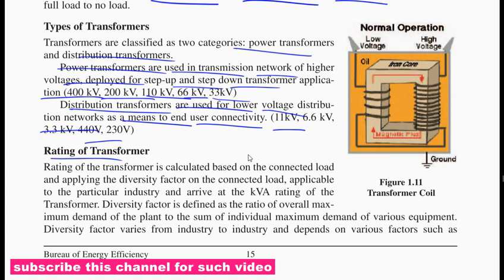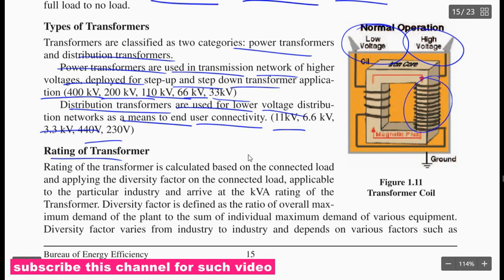The transformer has coils: a low voltage coil and a high voltage coil. This is called the high voltage coil, this is called the low voltage coil. Rating of a transformer is calculated based on the connected load and applying the diversity factor of the connected load applicable to the transformer, particular to the industry, and arriving at the kVA rating of the transformer.